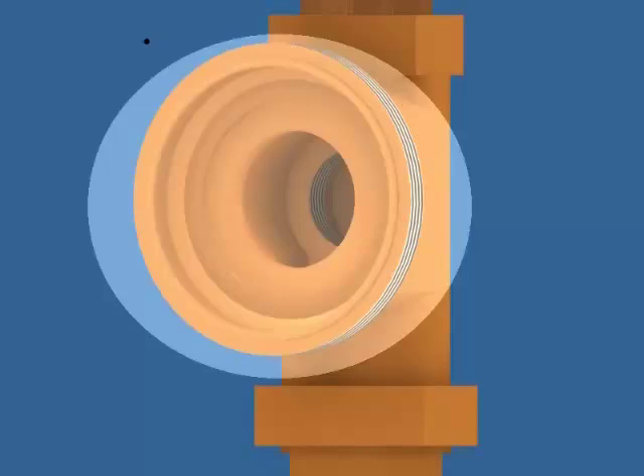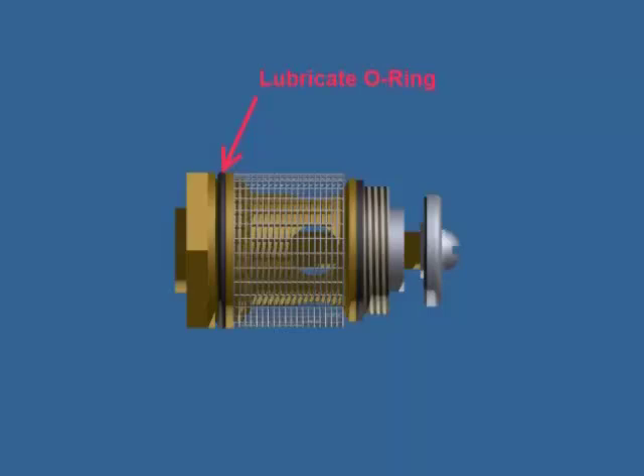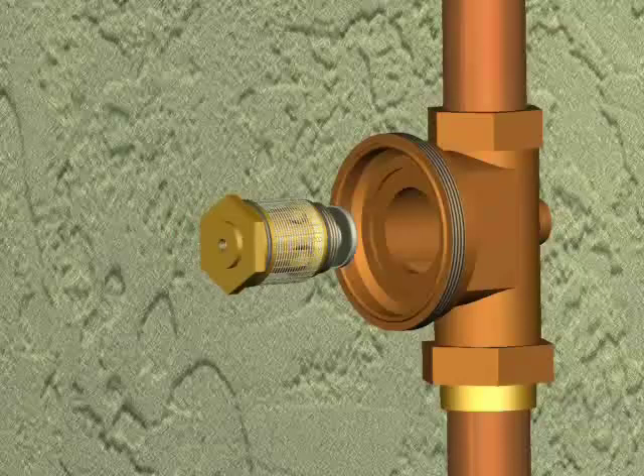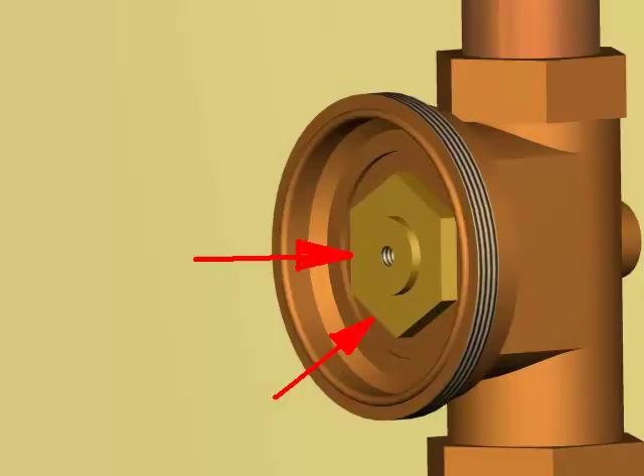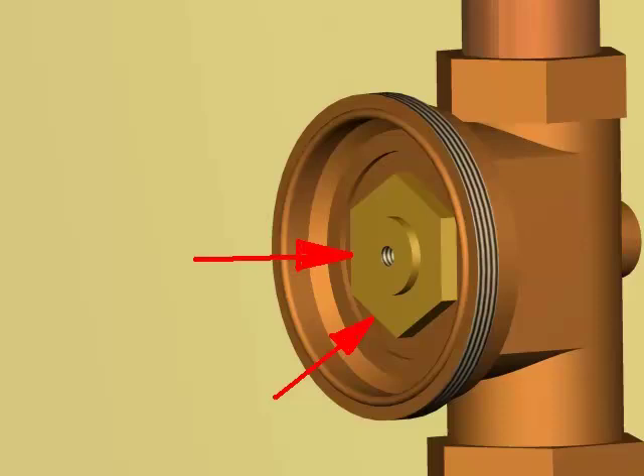Using the grease in the repair kit, you will lubricate the O-ring near the top of the replacement cartridge. You will want to make sure your screen and your cartridge gasket are on the new cartridge and thread it into the body. Tighten the cartridge with your socket or your wrench. Take care not to damage the top of the cartridge.